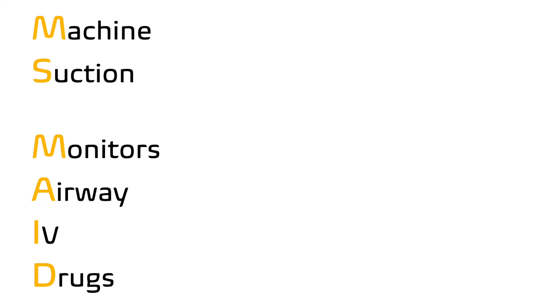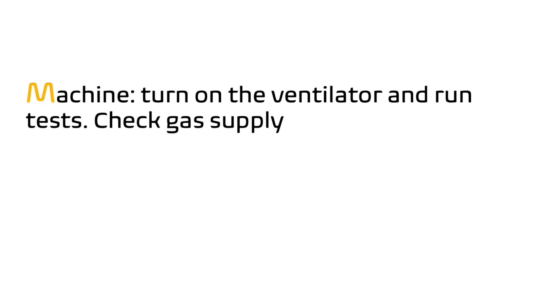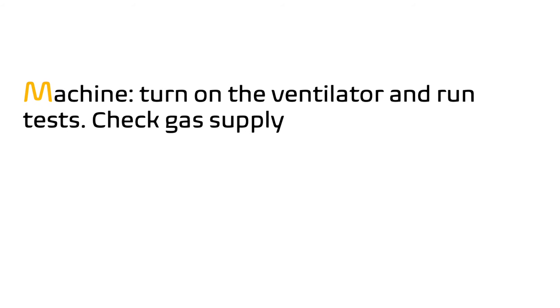Here we have a really helpful mnemonic that everyone always teaches called MS MAID. These are all the things that you need to have ready before bringing a patient back to the OR, and we will go through them in this order. First we have M, standing for Machine, which essentially means turning on the ventilator and running all of the checks.